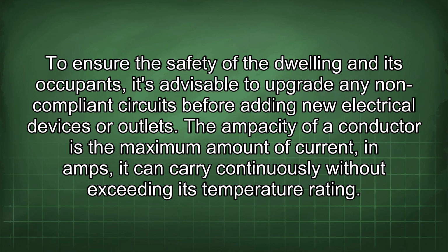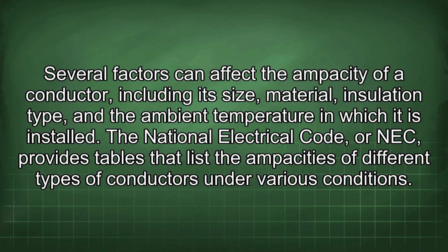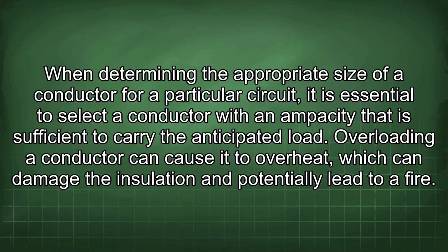electrical devices or outlets. The ampacity of a conductor is the maximum amount of current, in amps, it can carry continuously without exceeding its temperature rating. Several factors can affect the ampacity of a conductor, including its size, material, insulation type, and the ambient temperature in which it is installed. The National Electrical Code, or NEC, provides tables that list the ampacities of different types of conductors under various conditions. When determining the appropriate size of a conductor for a particular circuit, it is essential to select a conductor with an ampacity that is sufficient to carry the anticipated load.